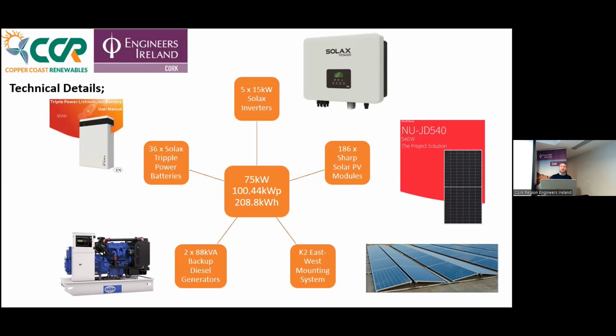So what it means is when you're in the northern hemisphere or further in the southern, it doesn't matter. But as you push up towards the northern latitudes, you're getting less and less sunlight. So for your CapEx investment, you can take advantage of the inverter's AC-DC ratio and push up to 100. So we've 75 kilowatts of inverters, but we've 100 kilowatts of DC. To get a 1:1 ratio, we would have needed an extra inverter. But during the middle of winter, when solar production is down, we're not getting any advantage of that, but we've put all the CapEx in. And during the summer, we would be getting the advantage of it, but we don't have the load. So it's always a matter of taking a measured approach with the data that's available and then filtering your best usage case back into the data that's provided to come up with your AC-DC ratio to offset as much as possible the client's load.